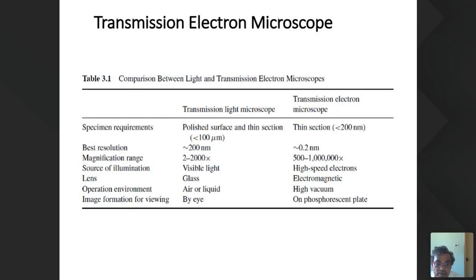So this is a comparison with the light microscope. Everything is available in any book. So what is the fundamental operating principle? The top portion of the column is similar to that of the SEM. The electrons are produced and are accelerated down the column by a voltage differential in the electron gun, typically 100 to 400 kilovolts. The column must be kept under vacuum while the microscope is operating, because otherwise the beam will get diverged. As the beam passes down the microscope column, it is focused by variable strength electromagnetic condenser lenses. These condenser lenses can either focus the beam to a fine spot on the sample or flood a much larger portion of the sample with a parallel beam of electrons.